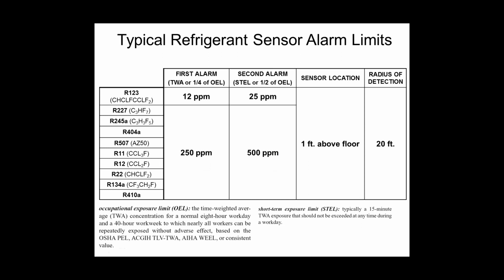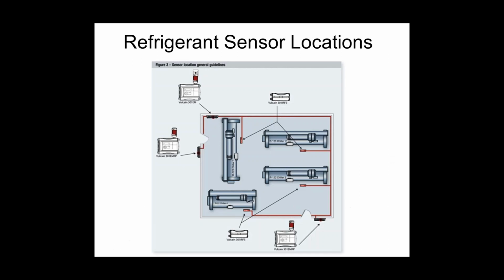You need to locate the sensors 1 foot above the floor. That is because refrigerant is much denser than air and will sink to the floor first. So you need to alarm there first, measure it in the first place it's probably going to end up. And most manufacturers of sensors will tell you they have about a 20-foot radius of detection to pick up these gases. So that usually all boils down to a mechanical room that looks like this. I typically end up with 1 sensor per chiller.